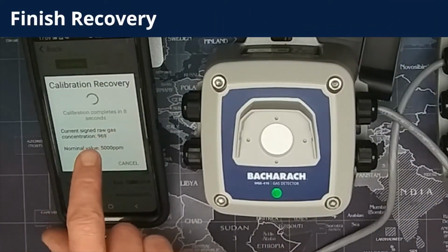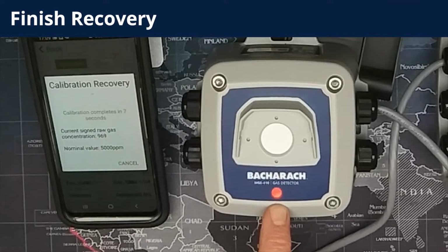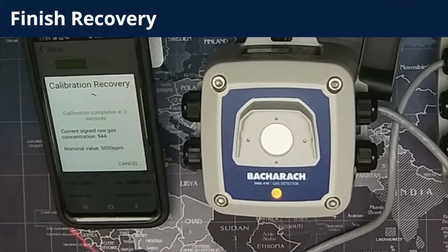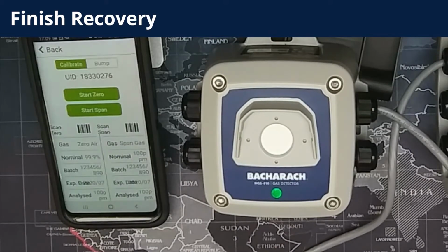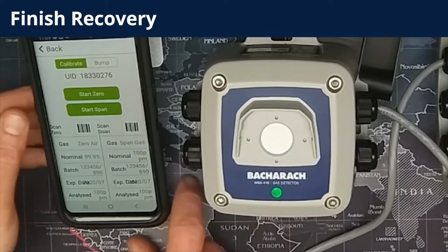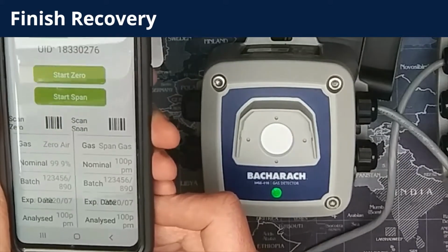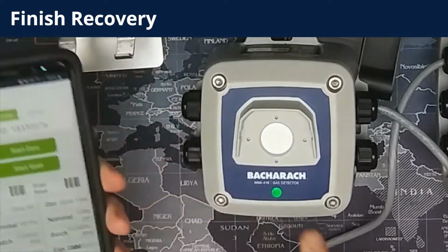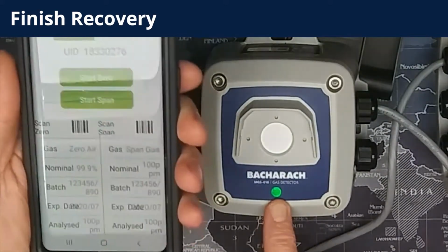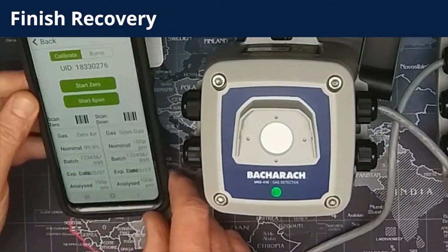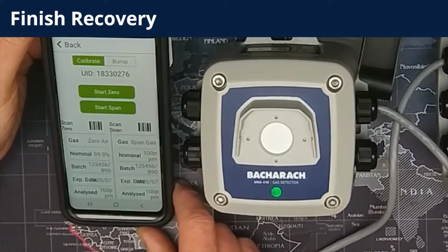Okay, it's now approaching 0 seconds, and the LED sequence is as detailed in the manual. Once it gets down to 0, it's completely finished its calibration recovery, takes it back to the calibration screen, and the LED is solid green. That is the calibration complete.